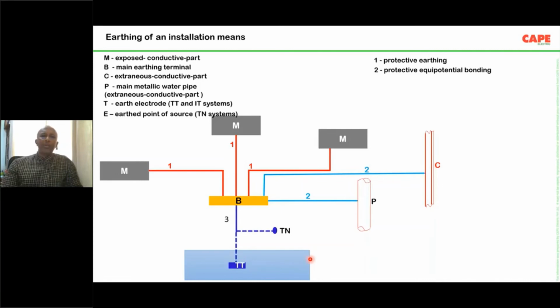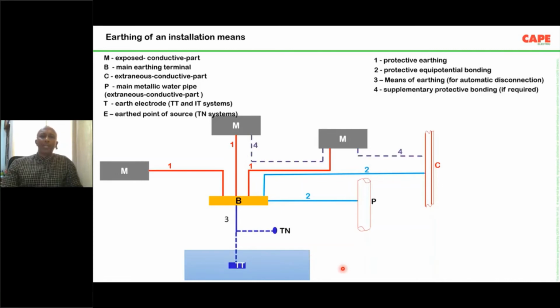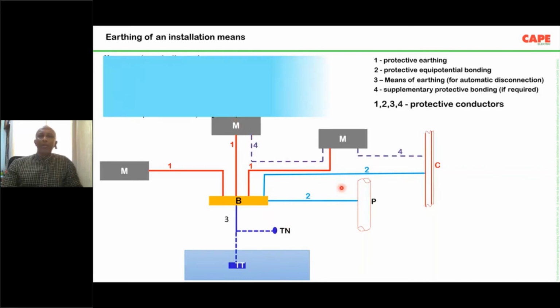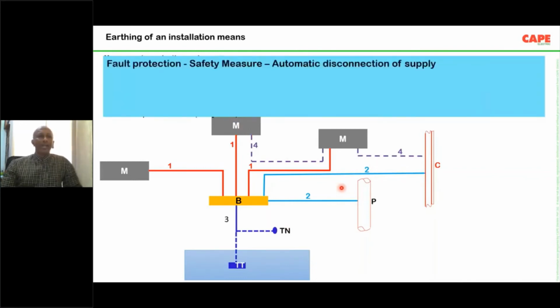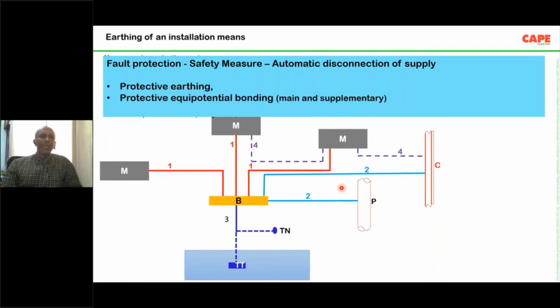And the last one is called measures for automatic disconnection. And here, item number 4 is called supplementary bonding. I will go into it in detail in the next slide. Say, for example, earthing in low voltage system. What does it mean? Fault protection is achieved by a safety measure called automatic disconnection of supply. Automatic disconnection of supply is achieved by protective earthing, protective equipotential bonding, and automatic disconnection of supply within the specified time.